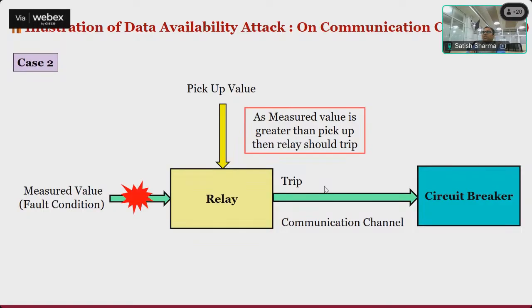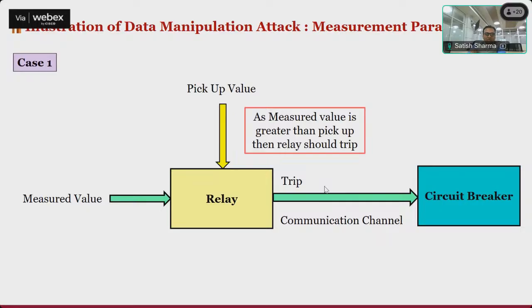Another attack can happen at the measured value. So we are measuring certain values, and if we attack those values, the relay will never see that some fault has been there. So we can attack the communication of the measured value, and once it has been transmitted to the relay, in between it can be modified, it can be stopped, it can be delayed. So those kinds of attacks are there, and in that case the relay's response to trip the faulted section under the fault condition will either not happen at all, because the control room doesn't even know that there is a faulted condition, or it may be a delayed response and lead to a more severe fault condition.